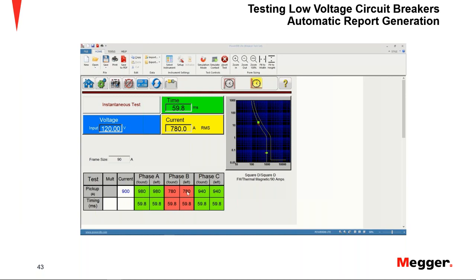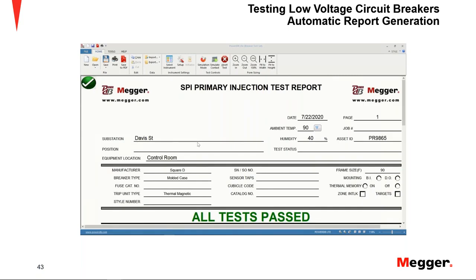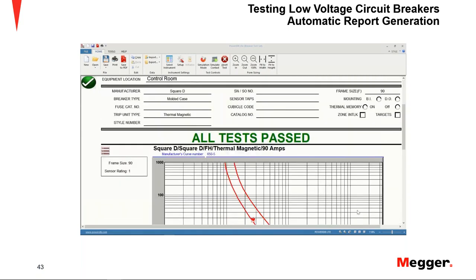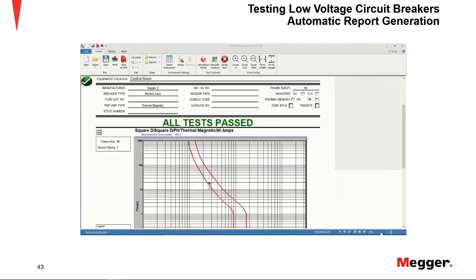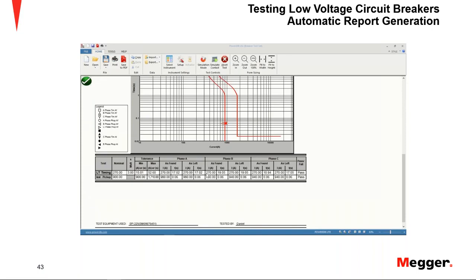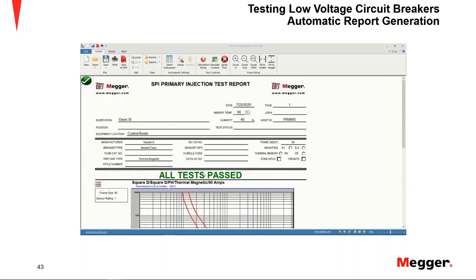So I go back to the testing screen. Let's say again, we did some maintenance, some change in settings maybe, and let's retest phase B. And now we're gonna trip that breaker inside the limits of the curve. So how will that look in the report? So doing the pulses, increasing 20 amps each time. Look at the time, it is 5 cycles per pulse. It trips, and now it passed. Right? So my 3 phases pass. My previous as found results are still in my report, but now the indication is that all tests pass and are within the limits established in the TCC curve.